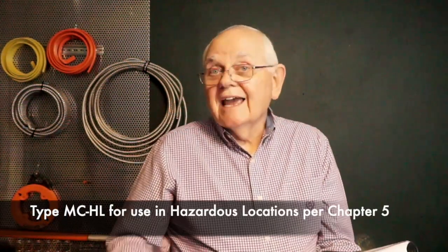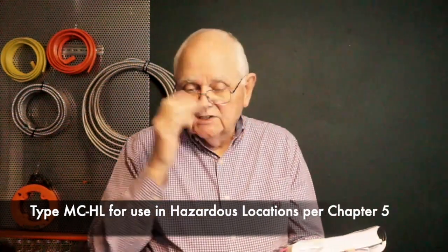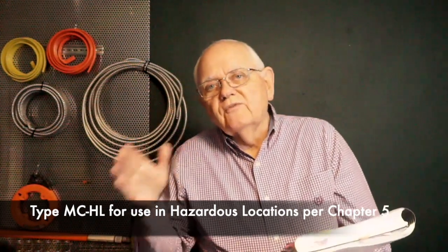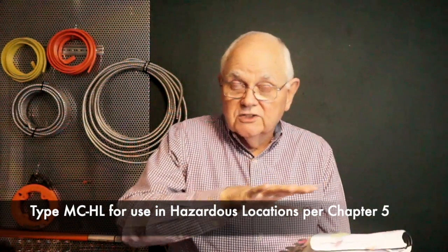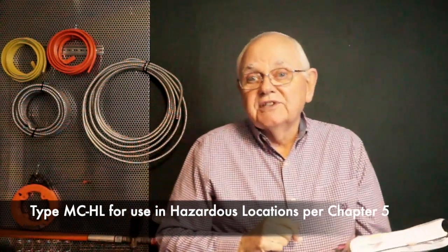My general provisions, then, I can use it for services, feeders, branch circuits, power, lighting, indoors, outdoors, direct buried where identified for use, as we said. I can use it in cable tray. I can use it inside of any raceway. I can use it in hazardous classified locations, MC-HL, suitable for use in hazardous locations, in other words. So we'd have to go back to Chapter 5 to our hazardous classified locations articles and find where we can specifically use our MC-HL cable with the appropriate listed fittings, of course. I can use it as aerial cable on a messenger, in dry locations embedded in plaster finish on brick, in wet locations where a corrosion-resistant jacket is provided over the metallic covering.